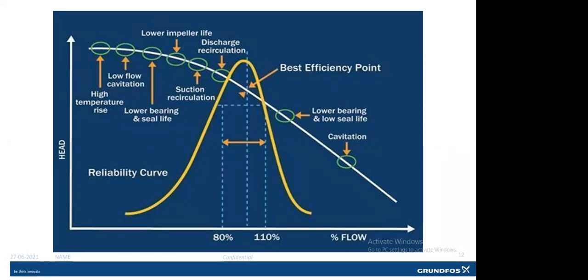And if, for example, the pump is designed at a certain head and is operated at a lower head, it tends to first cause cavitation and lower bearing and seal life. So it's always recommended to operate the pump within 80% to 110% of the flow capacity at the best efficiency point. If the duty point shifts for any other reason, the pump performance deteriorates, or we can say the pump efficiency drops.